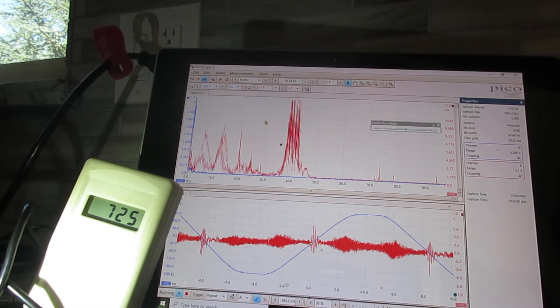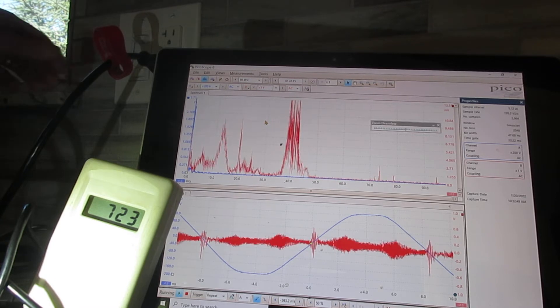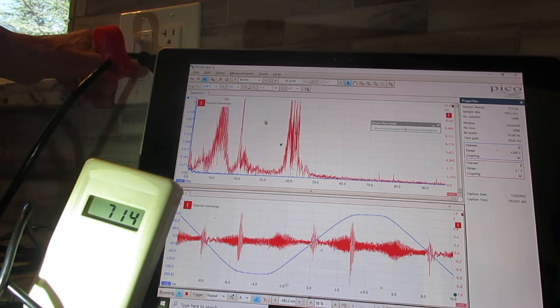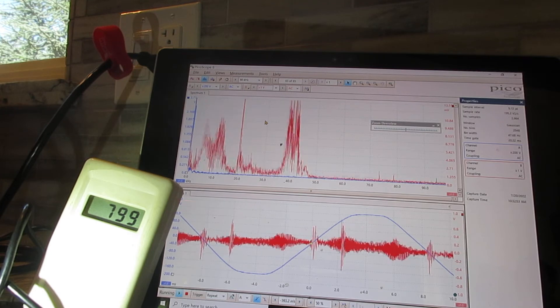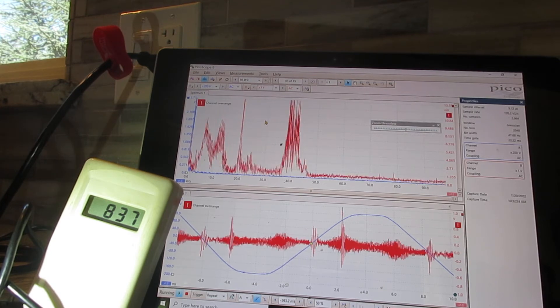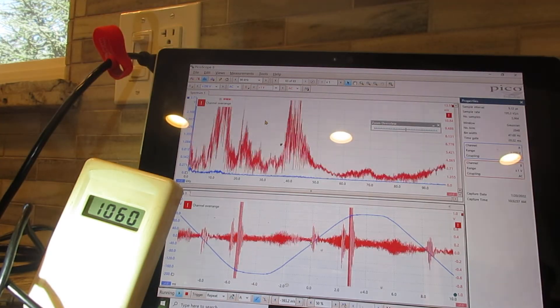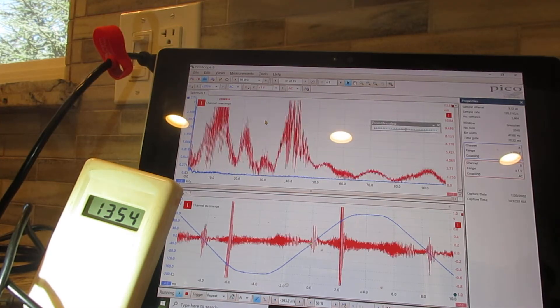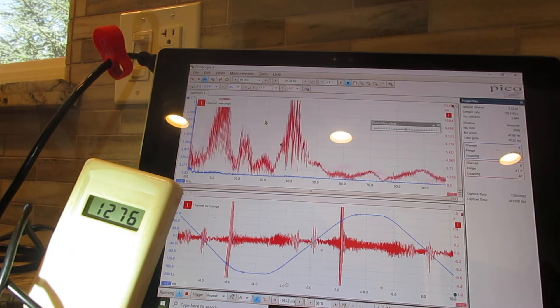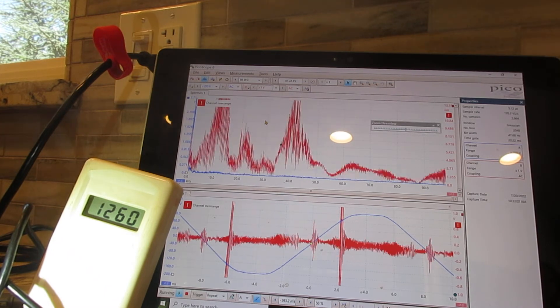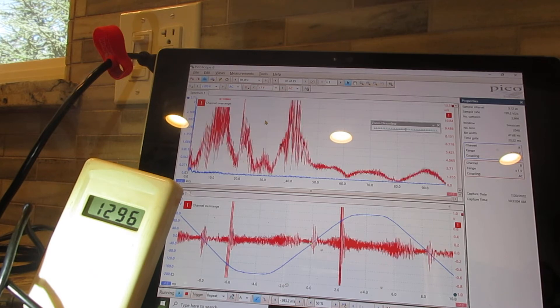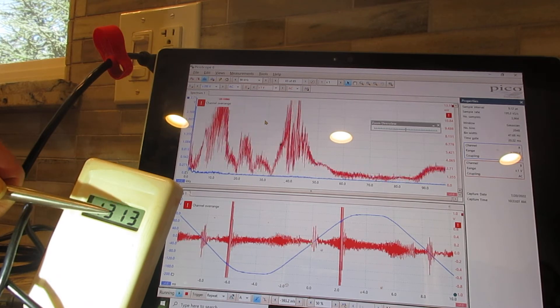Okay, so that's just what's coming in from next door. Now we're going to turn on a dimmer switch here at the kitchen counter and another dimmer switch. So just two dimmer switches and there's a lot more. We could turn on more. Now we're at 1260, which is definitely a hazard.